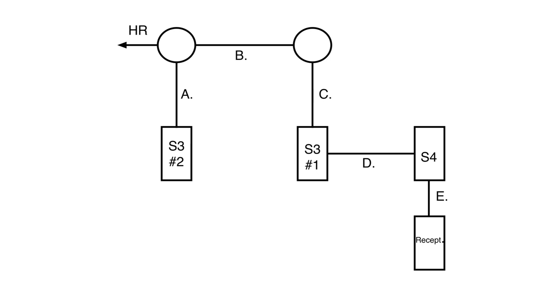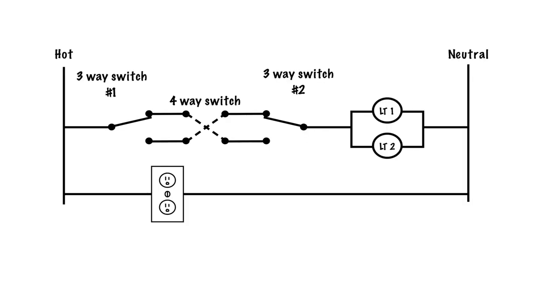Our first step is to draw out a schematic which shows electrically how the circuit works. Here is our schematic. Whenever we have three-way switches we always have two three-way switches — one on one side going from the hot to a common, then through the switch to a traveler. On the other three-way switch, same thing: travelers, common, common to the lights, lights to the neutral.